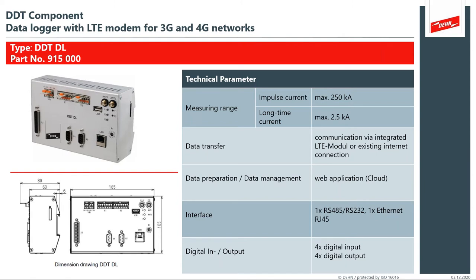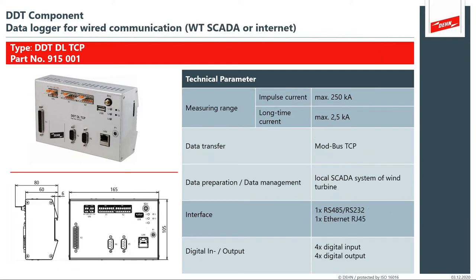The data logger is really the brain of the system. It captures the data and reports it back to the cloud application. It's a DIN rail mount requiring 24-volt power, so it would be installed inside the nacelle — probably in the control cabinet interface you already have. It's not taking up a tremendous amount of real estate, but it's providing this particular service. We also have versions wired specifically for SCADA or internet interface, but the data logger still performs these functions and is installed in the nacelle.